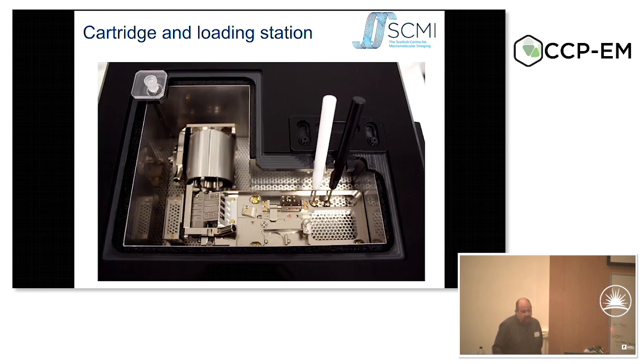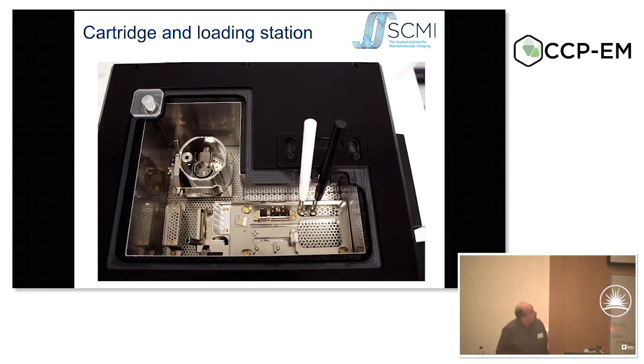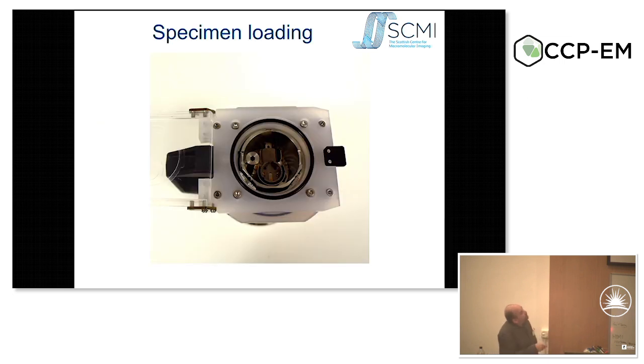You can see the grid sits in here, and it's held in place by a clip ring. It's loaded into this cartridge in a very well-designed ergonomic loading station. So we have the tools here, the cartridge sits here, and this is where we do the clipping. Once the grid is clipped into this cartridge, it gets moved into this magazine here. Then that gets slipped into this cup here, which is then lifted out into the transfer cup, which can then be loaded into the microscope.